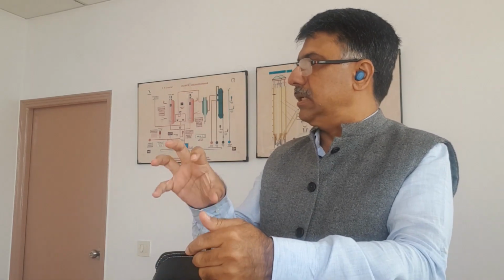When I said among components, the inverter is a key component. You can have two types of inverters. One which converts battery DC into AC - that would be a hybrid inverter or an off-grid inverter. But if the load consumption is higher during the day, then to charge the batteries we'll have some on-grid inverters, which will couple with the hybrid or off-grid inverter and give us an AC coupled system.